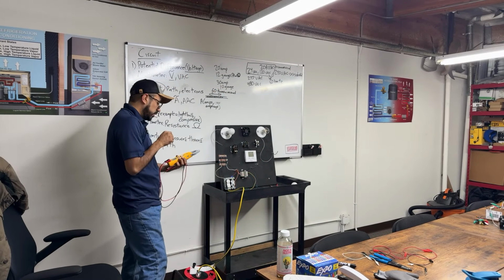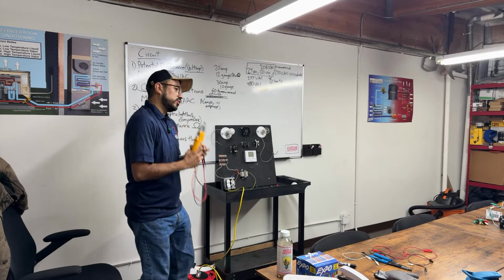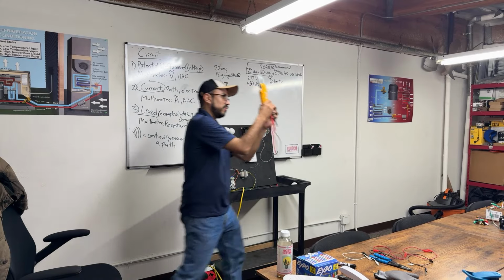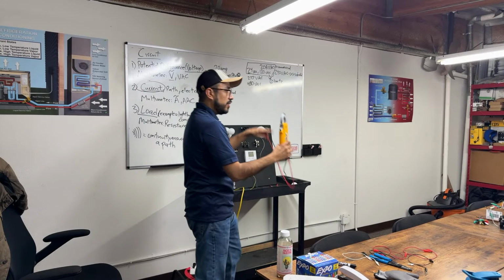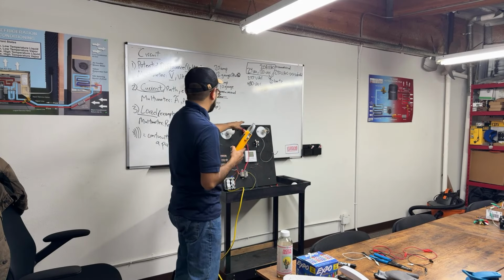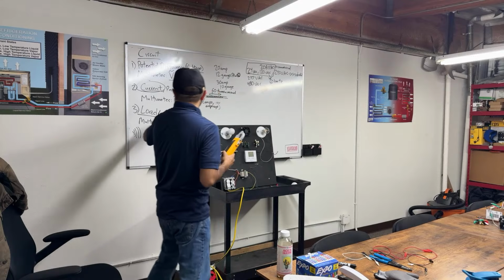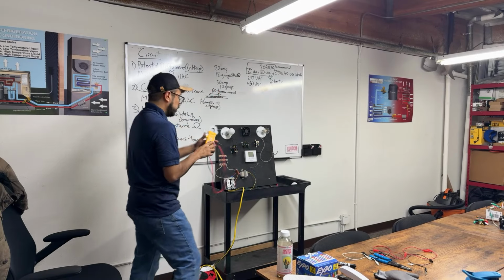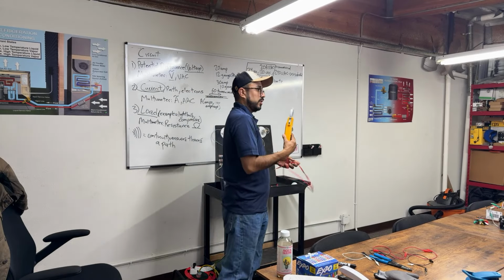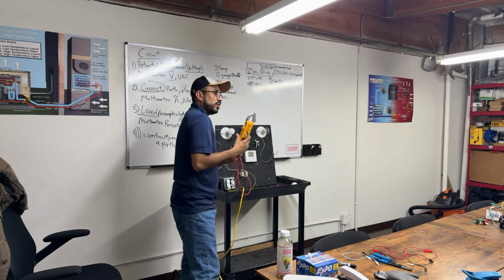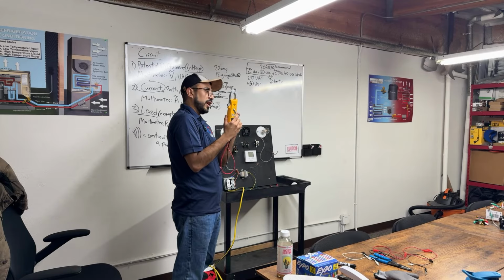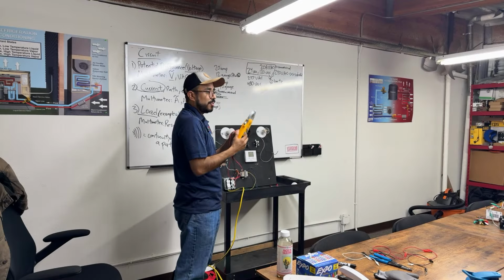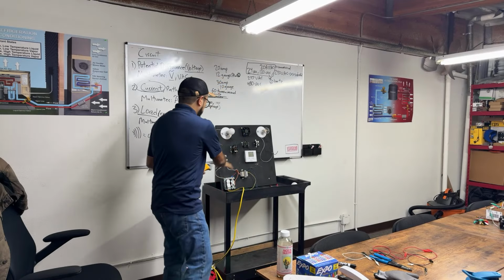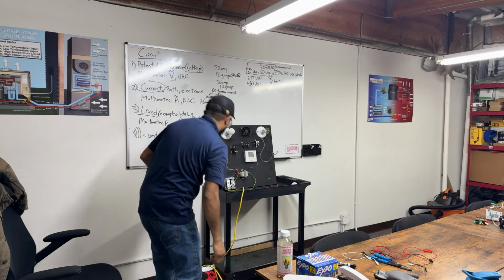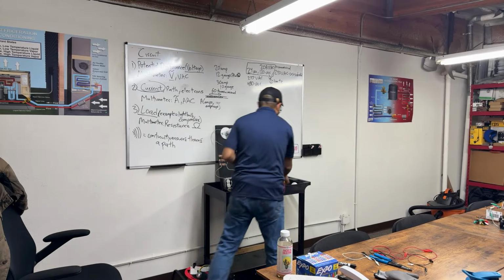Another thing - when you're going to check voltage, make sure it's set to VAC. Because if you have it set to resistance, which is the last thing we'll go over before we go down there... for example, with this load I need to put it on resistance. But if I'm checking power with it set that way, you'll end up blowing the little fuse inside the meter. It happens with some of these meters. Now let's see, no more power, what is it set to?